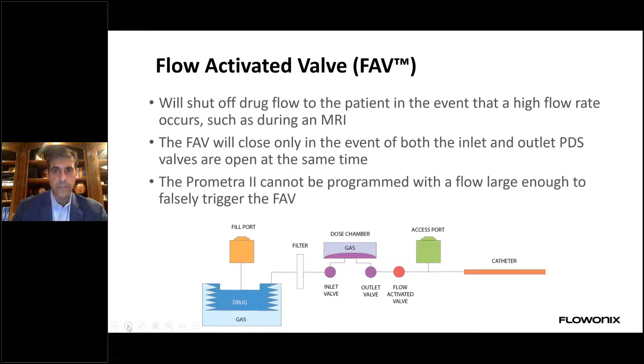This MRI protocol is for elective MRIs. Basically, prior to entering the MRI environment, the ProMetra 2 pump should be emptied of any drug except in a medical emergency. The patient then undergoes the MRI, and after the MRI, it is confirmed that both the inlet and outlet valve are closed, the pump is then refilled, and then restarted.